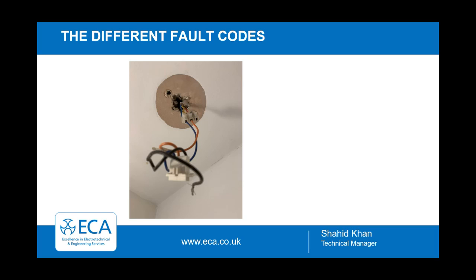What about this one? So that's the connections to a downlighter that have been made off with a bit of chock block. What do we reckon? I'd go for a C2. I'd say C2 for that one. Yeah, I'd agree with that. So the connections are not adequately enclosed. Regulation number wise, 526.1 or 526.5 would work in that instance.